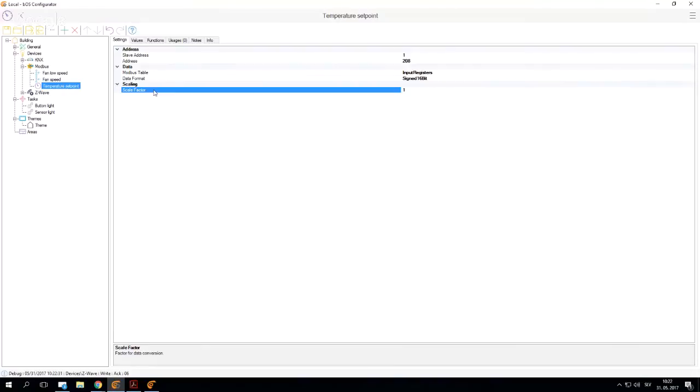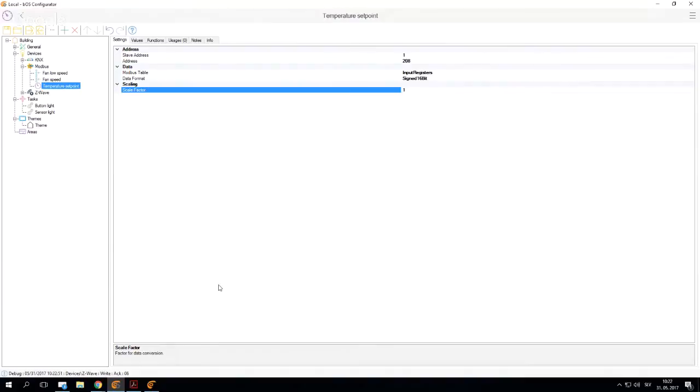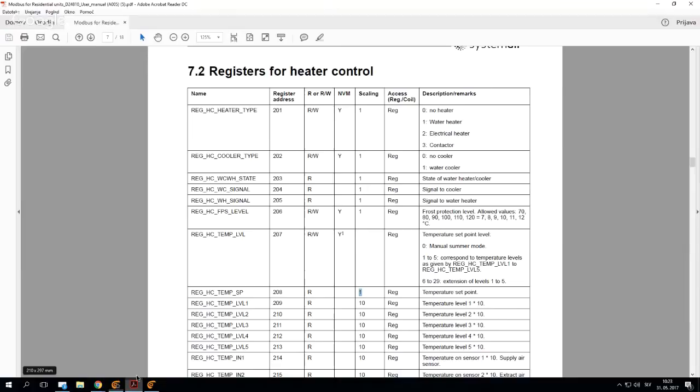We would use 1 and we would perhaps get a temperature of 25.5 degrees, and our scaling factor would be incorrect here. We would get a different value on our Modbus device, which would be 255, which is of course incorrect. So a scaling factor must be taken into consideration when importing and using temperatures.